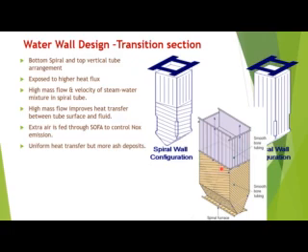In the water wall segment there is nucleate boiling, where the surface temperature is higher — almost 20 to 30 degrees centigrade above the saturation temperature — so the material needs to withstand high temperature and pressure. Due to the once-through technology, a thick-walled storage drum is not required, enabling shorter startups. High mass flow in water wall tubes gives uniform heat transfer between the tube surface and the fluid. There are also extra SOFA nozzles connected to the water wall.